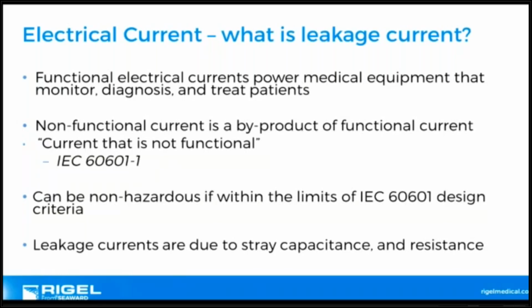In reality, in a plumbing system, you might turn the pressure up. That would be dielectric strength in the electrical world, to find out where that leak is. So we do a number of tests as per 60601 in the design criteria to try and make sure that we have those creepage levels, and manufacturers in particular of medical equipment have the adherence to make sure we have safe levels in this type of thing. Anyway, if this non-functional current, leakage current, defined by 60601, is within the safe limits of the 60601 design criteria, then everything is good. But leakage currents are due to this stray capacitance and dielectric resistance within medical equipment.